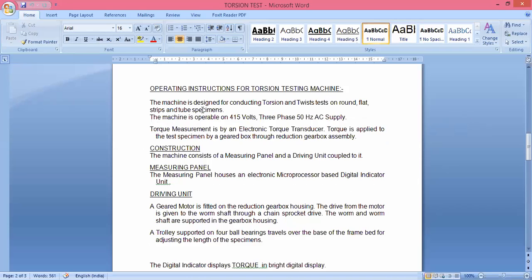It is designed for conducting torsion and twist tests on round, flat, strip, and tube specimens. What we've shown is a cylindrical specimen with two square dumbbell-shaped ends, required for holding the specimen in the vise. But if required, you can also use a flat workpiece or strips as specimens. The only mandatory requirement is that all the ends of these specimens should be made square and have dimensions suitable for accommodating inside the vise.